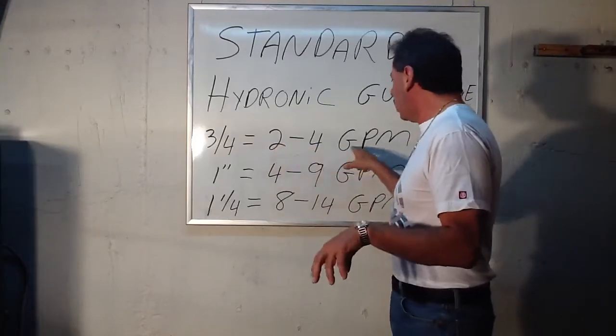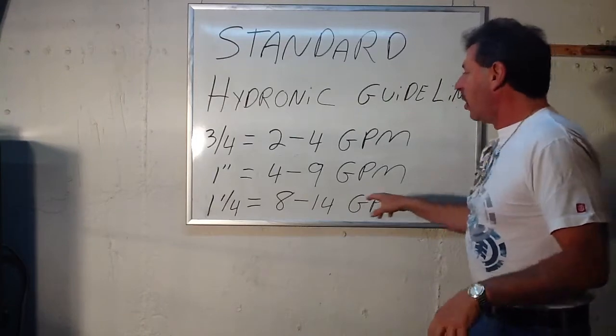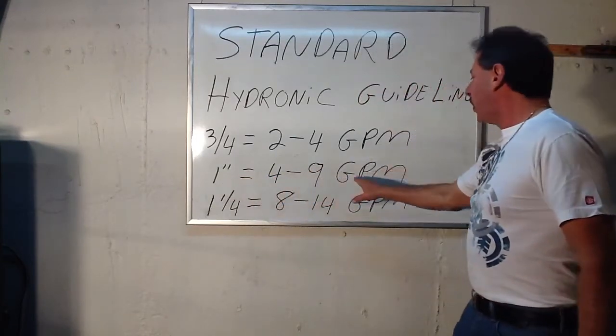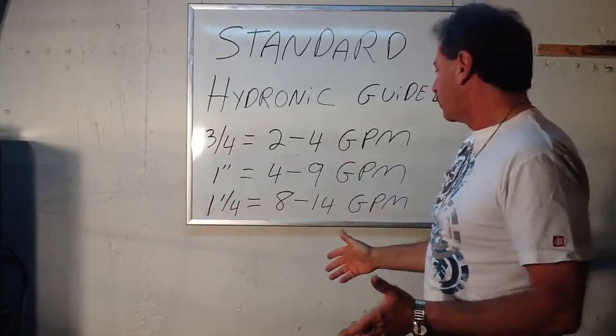But that's normal for baseboard. If you're doing a larger system, just so you know the guidelines, one inch will give you four to nine gallons per minute, a flow rate of between four and nine gallons per minute.